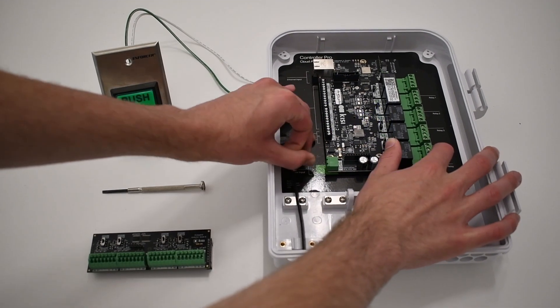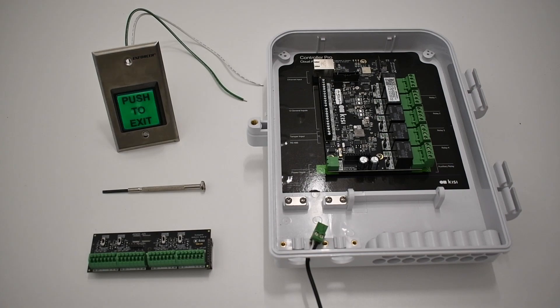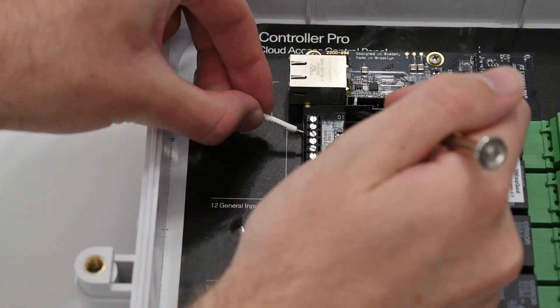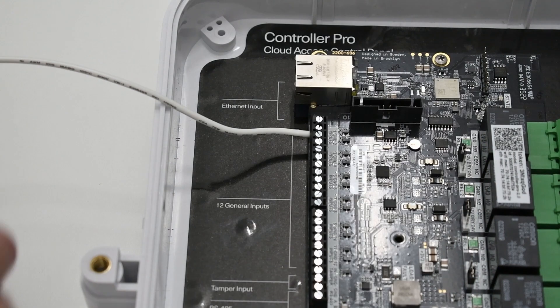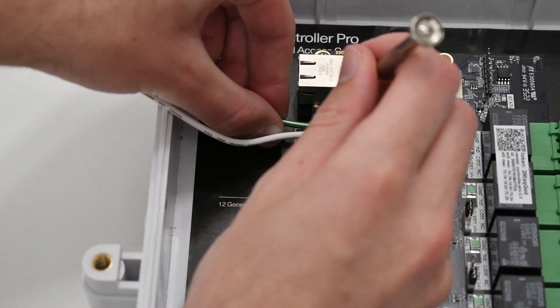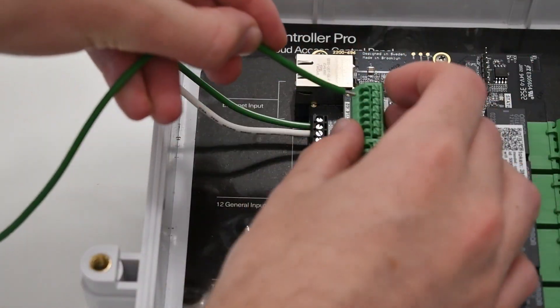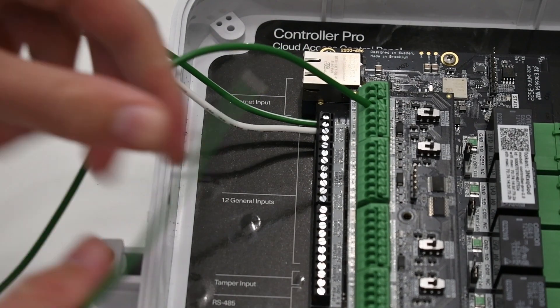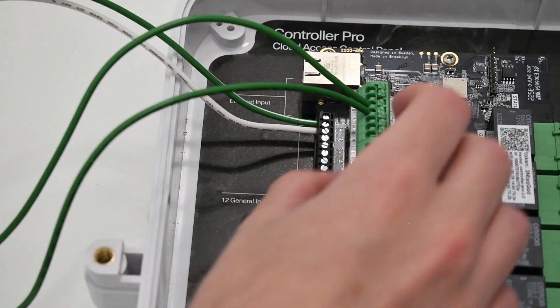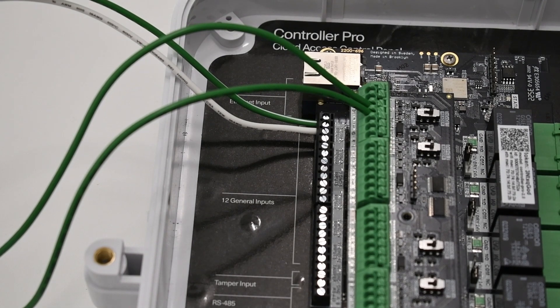Ensure the controller is unplugged, and identify the general input pins on the left side of the Kisi Controller Pro 2. Now connect the COM output to one of the GND ports of the controller. Then connect the NC output to one of the numbered general input ports on the controller. Connect the positive port to the positive terminal of a power source, and connect the negative port to the negative or ground terminal of a power source. Some push-to-exit buttons are simpler and only have positive and negative wires. In this case, just connect positive to an input pin and negative to a ground pin.